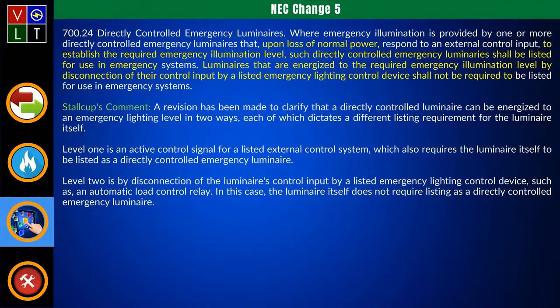All right. Yep. And then the last one we got for this week is 700.24. And what they did, they made a revision here to help clarify that a directly controlled luminaire can be energized to emergency lighting level in two ways, each of which dictates a different listing requirement for the luminaire itself. So they're going to give you two levels here. Level one is an active control signal from the listed external control system. And it also requires the luminaire itself to be listed as a directly controlled emergency luminaire. And level two is by disconnection of the luminaire's control input by a listed emergency lighting control device. And one of those control devices is an item like an automatic load control relay. Okay. So they're just giving you two levels.